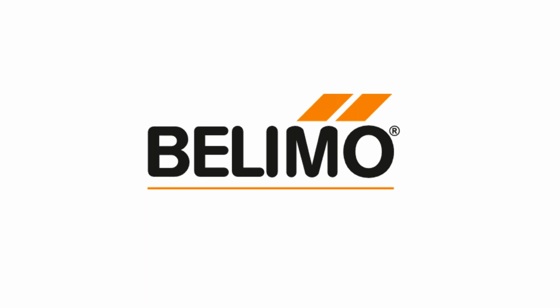Excellent, thank you. We'll take one last question here. How does water quality affect the performance of the energy valve? That's a good one. We use an ultrasonic wet flow meter today, which is a very robust, resilient flow meter. On top of that, we use our characterized control ball valve, the one we've been using since 1999, and it works very well in a wide array of water quality. Overall, we've had almost no issues with the quality of water within a normal HVAC spectrum. As long as everything else is operable in the system, these valves do not have an issue. You still get good accuracy and tolerances from the valve. No concerns there.